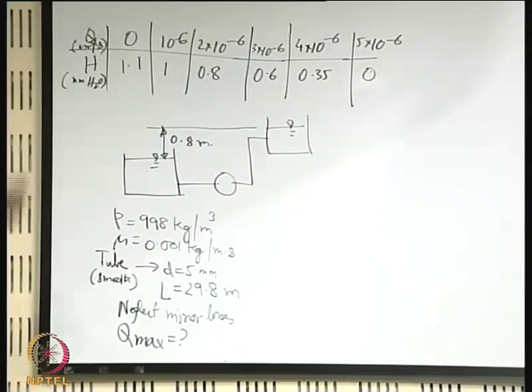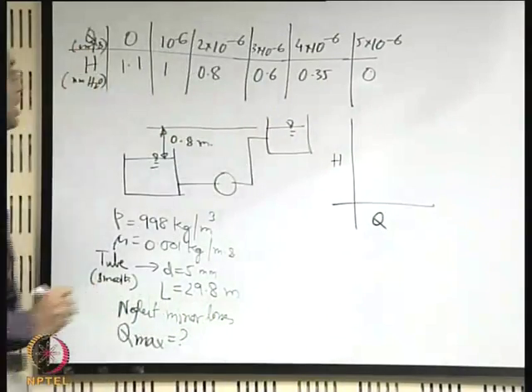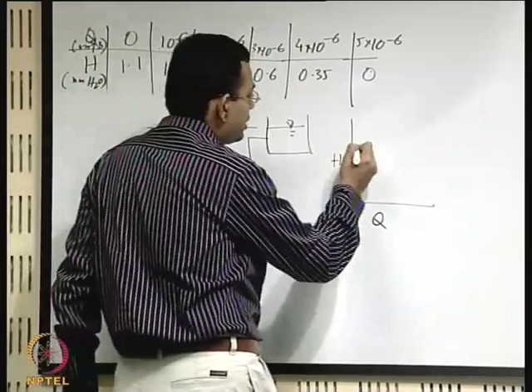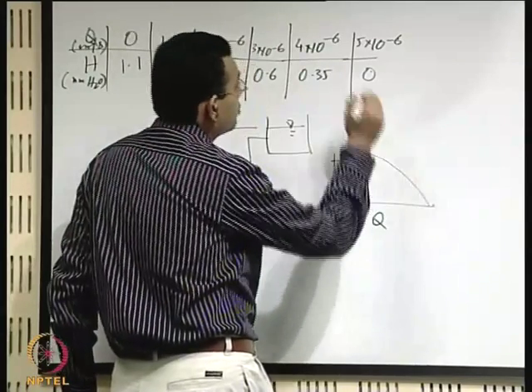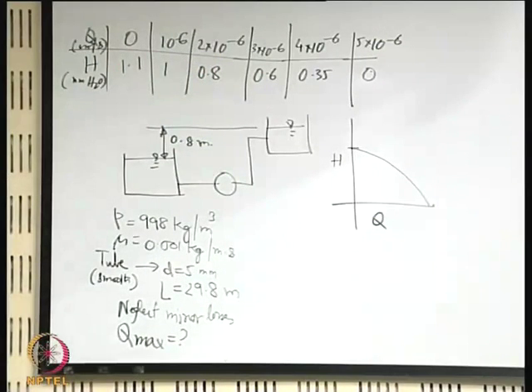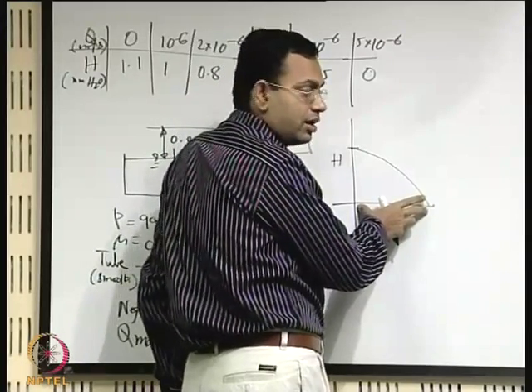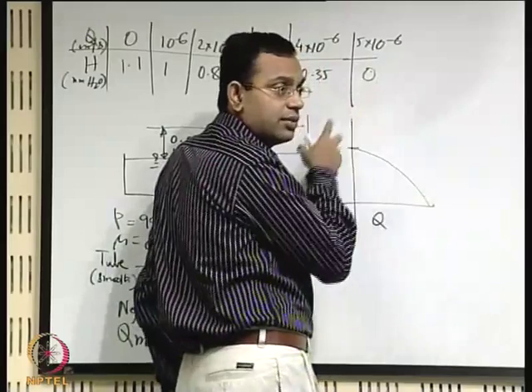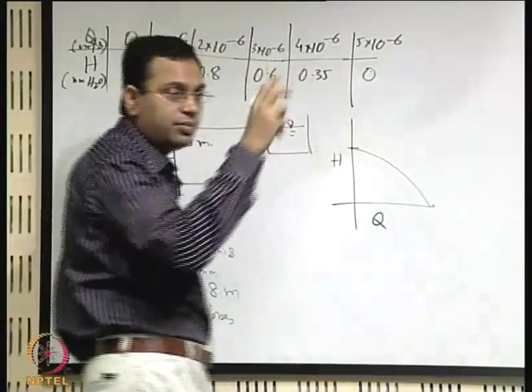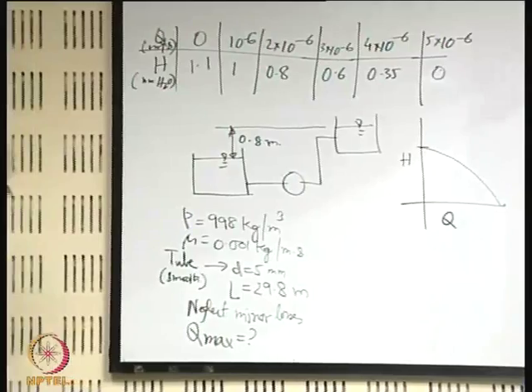Looking at the H-Q characteristics, when Q = 0 there is a particular head, and then H drops until at a particular Q the head becomes zero. So there is a maximum Q from the pump characteristic alone, but this maximum Q may not be achievable in the system because the pump must also satisfy all head losses in the system.